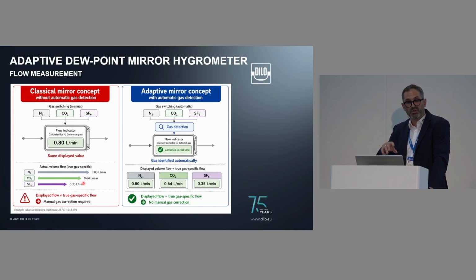So what you would need to do in that case is adapt the flow manually. But if you have an automatic gas detection, you know in the background all the densities and the heat conductivity and the specific heat capacity and so on. And you can tell the flow sensor, hey, it is now CO2, please use the correct parameters, and then the flow meter or the flow sensor displays the correct flow rate, volume flow rate.